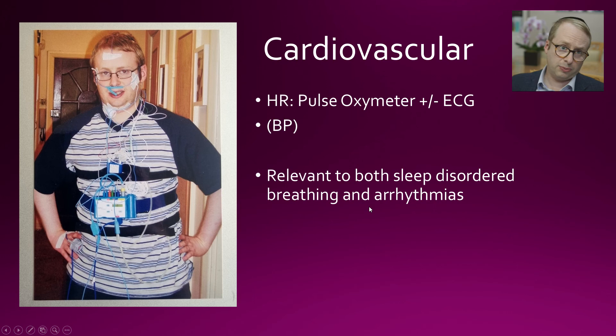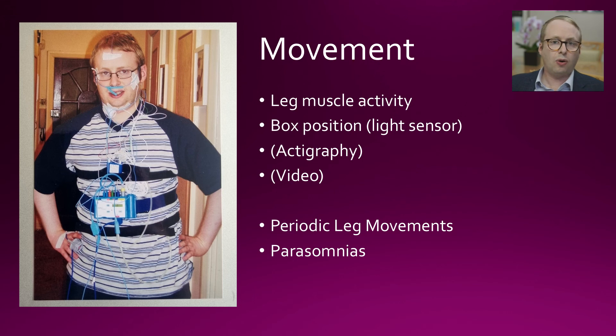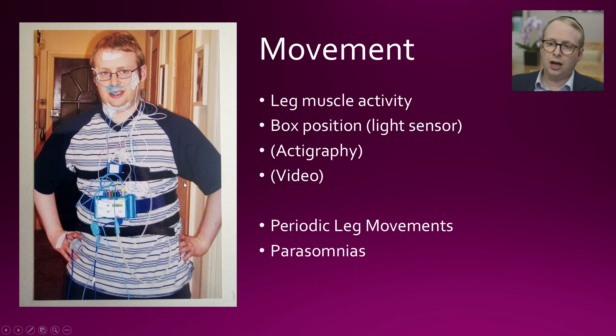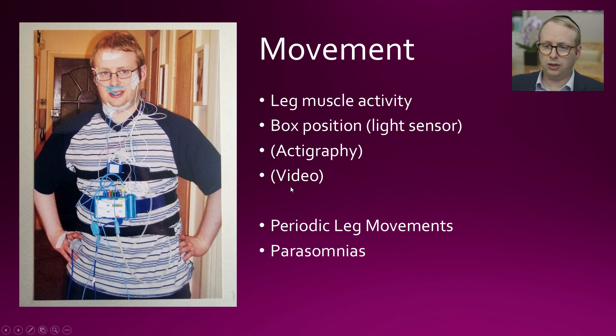In terms of movements, we have leg muscle activity detection via EMG, with a couple of leads going down to the legs. There's also an accelerometer in the box which looks at what position one is sleeping in — supine or on your side, for example. The box may also have a light sensor for when the lights are turned off, and there are options these days for actigraphy to record wrist movements, and of course video as well. These are all incredibly important for looking at periodic leg movements during sleep and the parasomnias — when things go bump in the middle of the night.